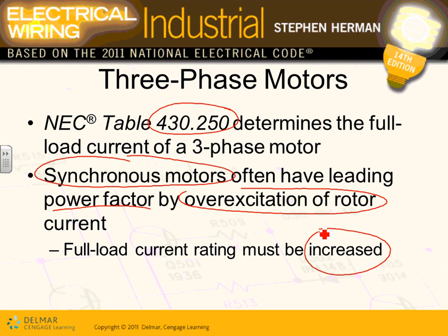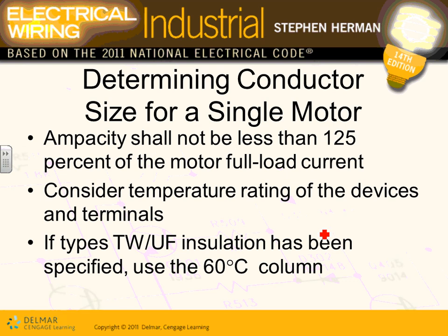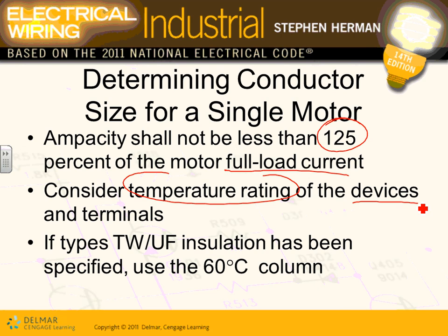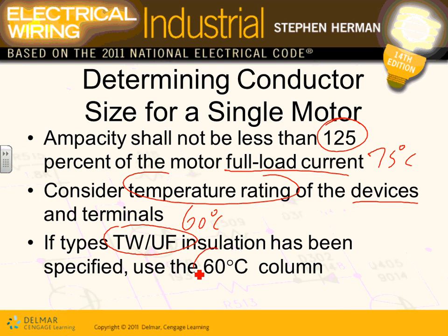When determining conductor size current, multiply the full load current by 125%. You also need to consider the temperature rating of the devices — typically the 75°C column. If you're using 60°C-rated conductors, you use the 60°C column. For engineers, most equipment is rated for 75°C.